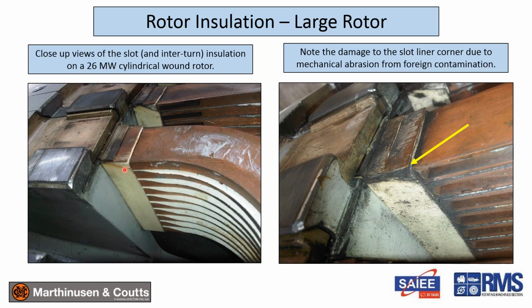Here's a close-up view. This is a 26 megawatt cylindrical rotor machine. You can see this is the slot insulation, and you can see how it's worn here. It's actually worn due to abrasion from contamination, but you can get an idea. And there's your turn insulation. So again here, big machine, low voltage, but you still require substantial insulation.